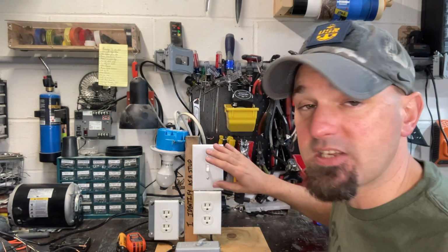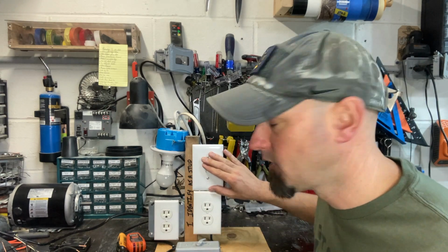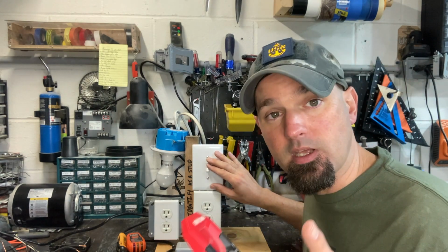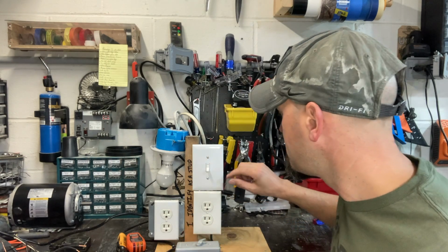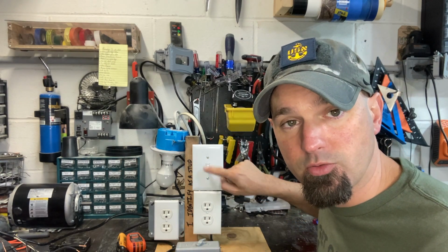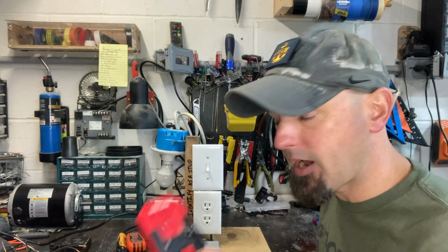So if that's the case, I'm going to have to take this plate off carefully, knowing it could possibly be live circuits. I'm going to have to take this faceplate off, which is just two screws, and then get this really close to the screws in order to detect if there's any voltage there.